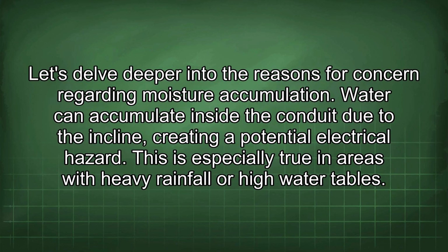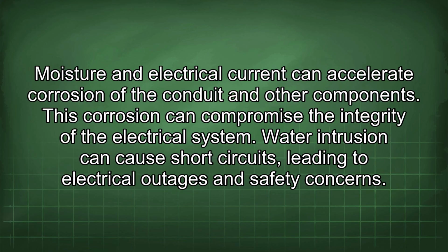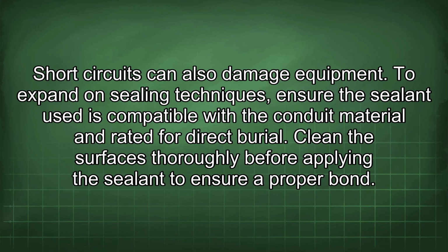Let's delve deeper into the reasons for concern regarding moisture accumulation. Water can accumulate inside the conduit due to the incline, creating a potential electrical hazard. This is especially true in areas with heavy rainfall or high water tables. Moisture and electrical current can accelerate corrosion of a conduit and other components. This corrosion can compromise the integrity of the electrical system. Water intrusion can cause short circuits, leading to electrical outages and safety concerns. Short circuits can also damage equipment.